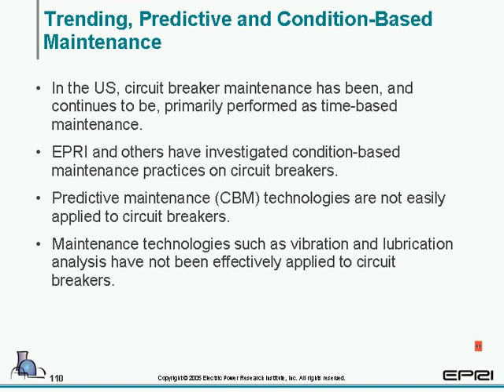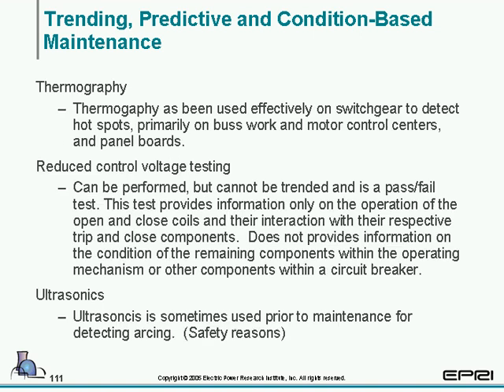Talking about trending, predictive and condition-based maintenance, EPRI's got a lot of questions over this through the years. Breaker maintenance has been and continues to be primarily time-based. It's just because of the nature of these older circuit breakers that we have in a lot of the plants. EPRI has investigated condition-based maintenance practices, but again, they're not easily applied to circuit breakers. Lubrication analysis, vibration, you know, some of these have been investigated, but they're not really all that effective.